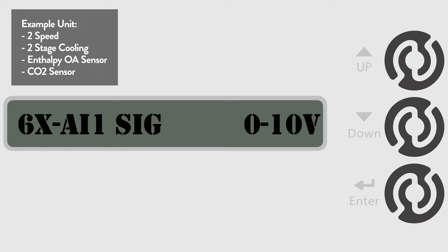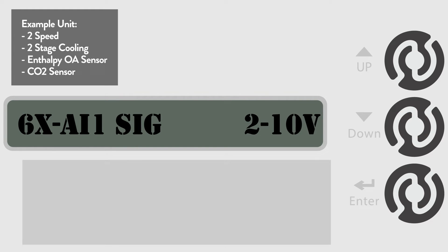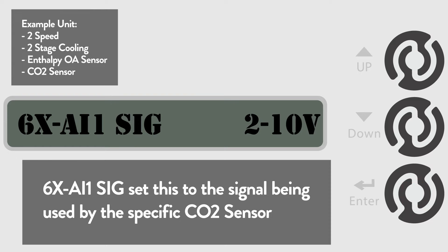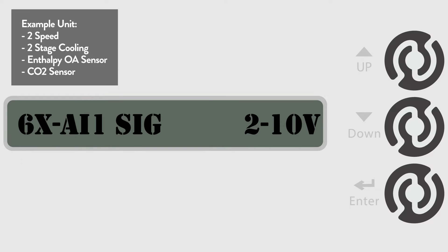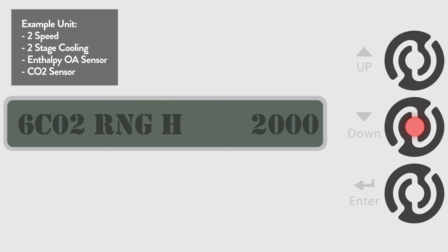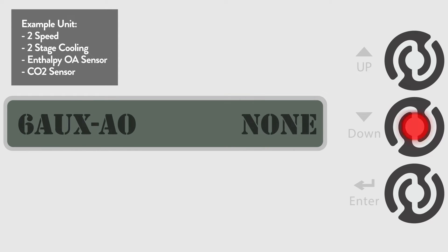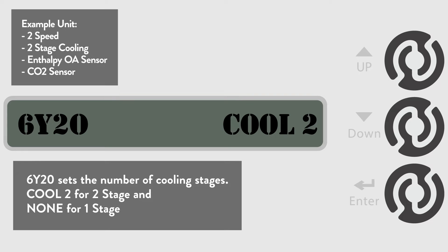Now scroll to the 6X-AI1 SIG menu to set what type of signal is sent to the CO2 sensor. The default is 0 to 10 volts, but for this example we are going to change it to 2 to 10 volts. Now let's go to 6Y20, which sets the number of cooling compressors. The default is COOL2 for two compressors. If your unit only has one compressor, change this setting to none. For this example we will leave it at two cooling stages.